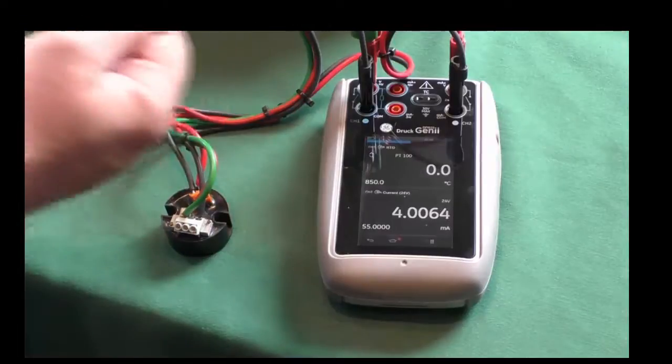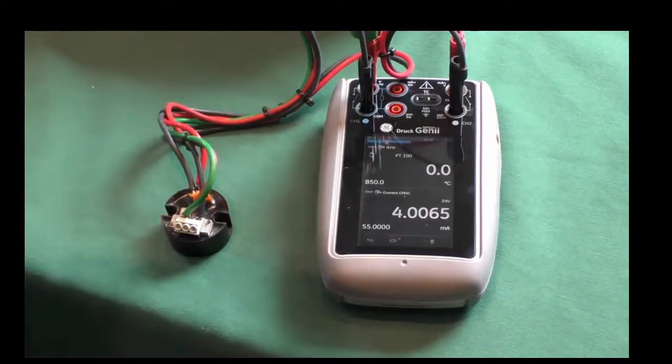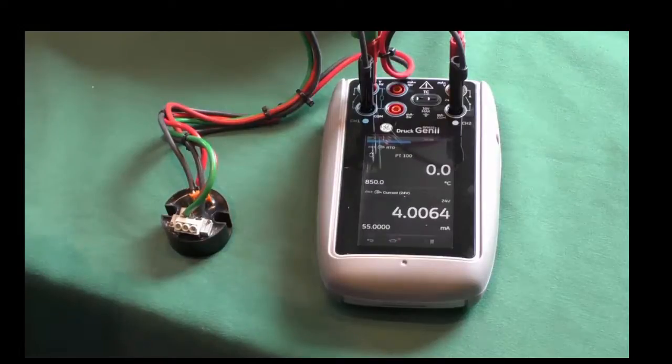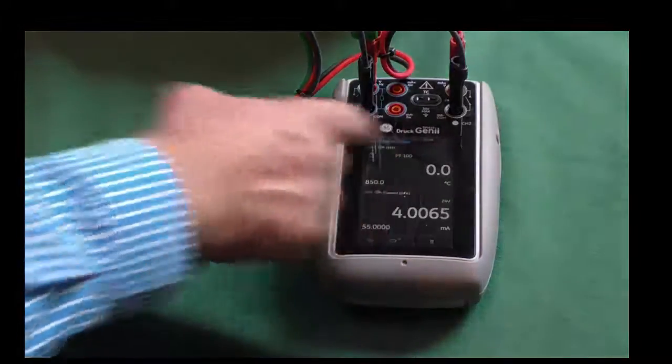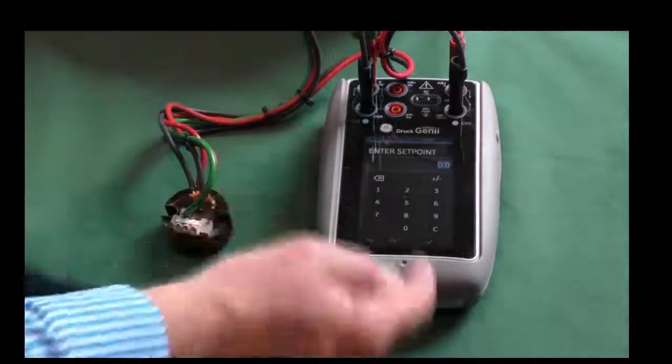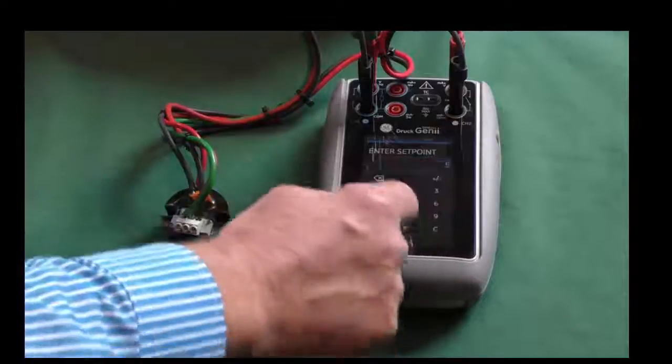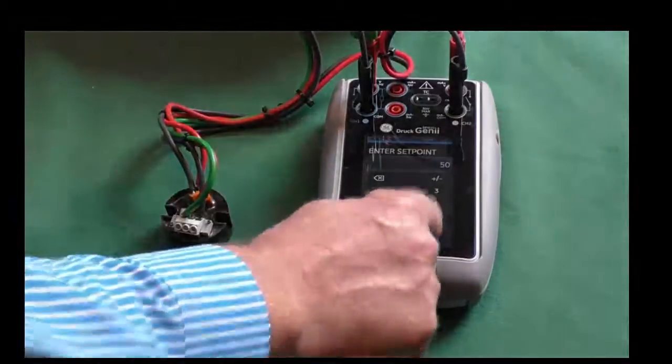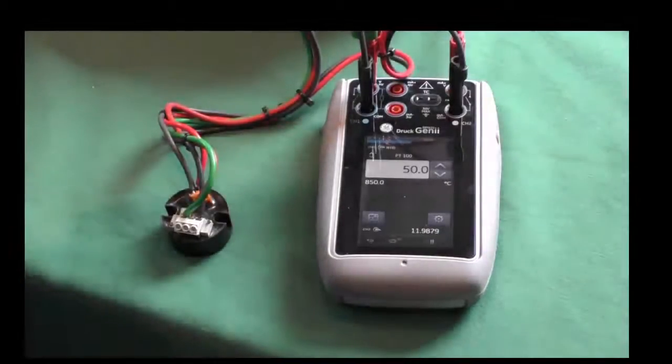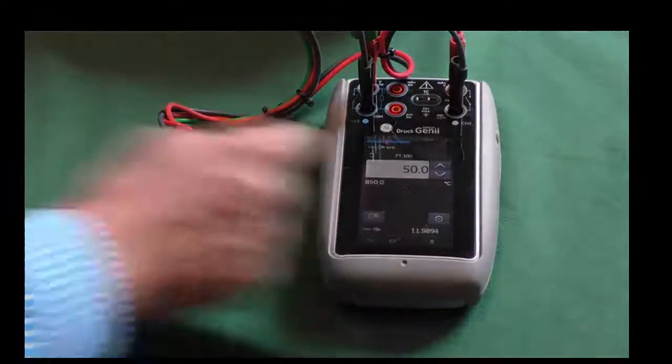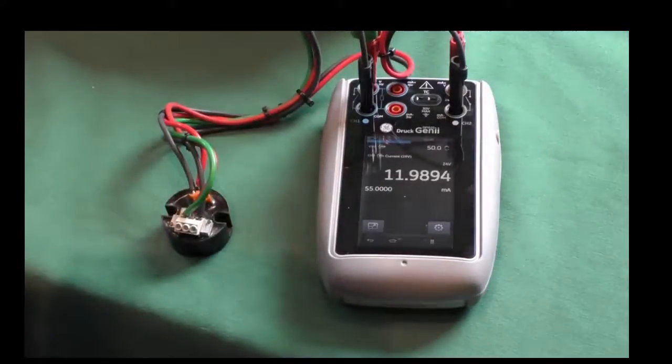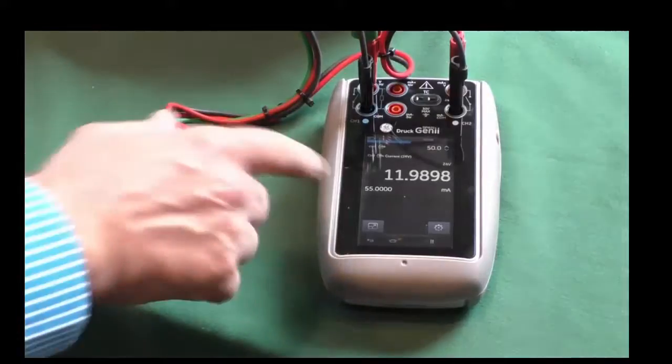So now what I want to do to calibrate this transmitter and set it up will be to simulate the temperatures. Now there's a number of ways that we can do that. We can simply go in and we can edit the value and type in what we need to do. And so if I want to go to 50 degrees C, I enter 50, hit the tick button, we now have 50 degrees C. I'll press on the bottom channel, you'll see there's nearly 12 milliamps, which is half of its range.